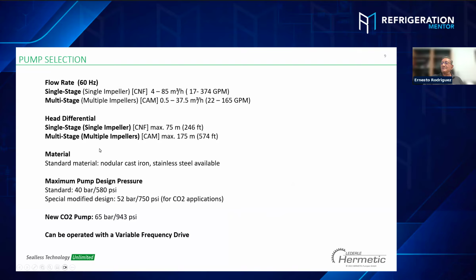But the advantage with the multi-impeller, we have a very high differential pressure. For example, we have in this sample 75 meters, 246 feet, versus 175 meters, 574 feet. That is the advantage we have with the multi-impeller pump.